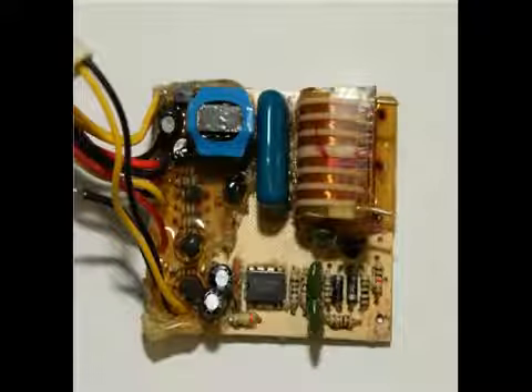Hole that you see here is where the third wire goes, for the wire that is for the sensor. There are 2 independent high voltage windings, opposite, 180 degrees out of phase. This is one of the white connectors, and we're going here to the high voltage box.